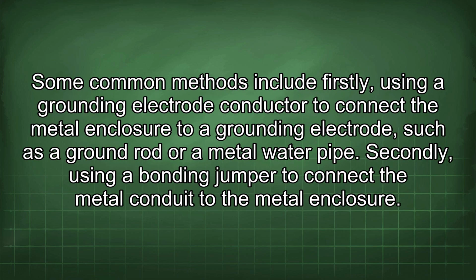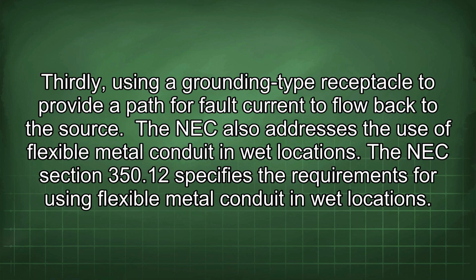Some common methods include firstly, using a grounding electrode conductor to connect the metal enclosure to a grounding electrode, such as a ground rod or a metal water pipe. Secondly, using a bonding jumper to connect the metal conduit to the metal enclosure. Thirdly, using a grounding type receptacle to provide a path for fault current to flow back to the source. The NEC also addresses the use of flexible metal conduit in wet locations.